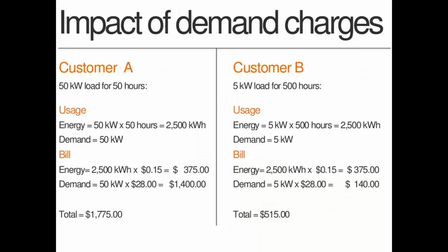So if we look at two customers, customer A and customer B, because we're really creative with the naming over here. One of them has a 50 kilowatt load that they're going to run this week for 50 hours. The other has a 5 kilowatt load that they're going to turn on for 500 hours. From an energy standpoint, 50 times 50 is 2,500 kilowatt hours, and 5 times 500 is 2,500 kilowatt hours. They're both going to buy the exact same amount of kilowatt hours. However, one's going to have a 50 kW demand, the other's going to have a 5 kW demand. On this particular utility bill, they're paying 15 cents a kilowatt hour. So that's $375 for either customer, and they're paying a $28 demand charge.